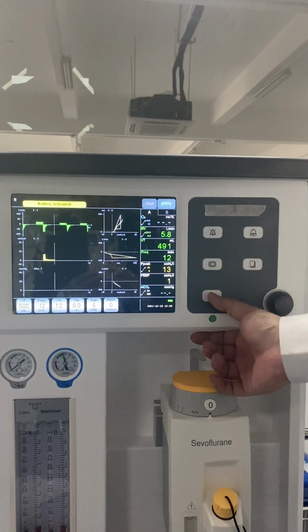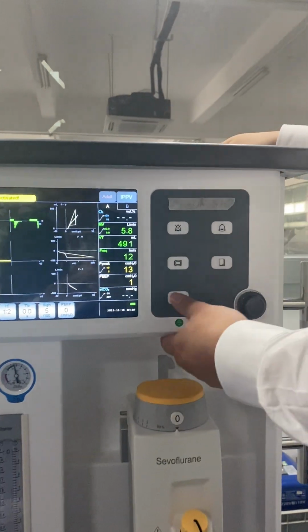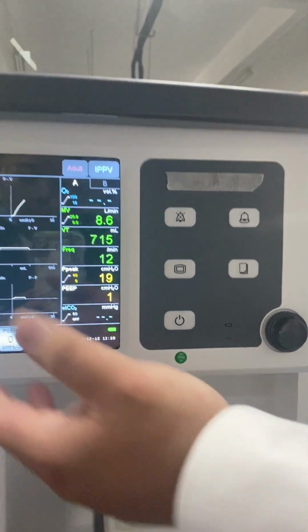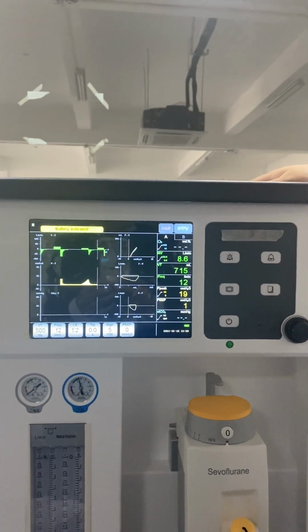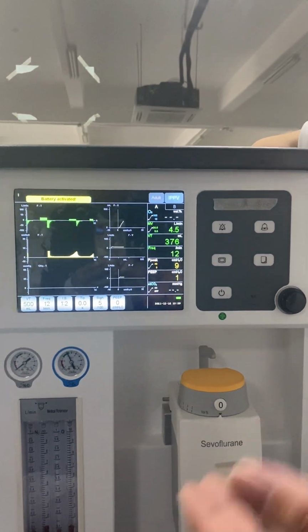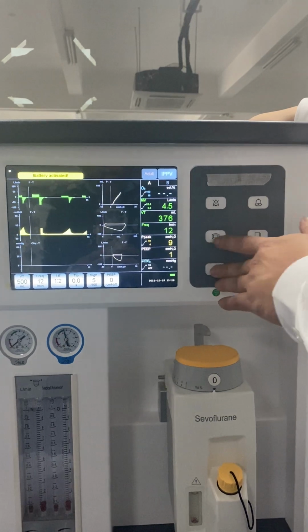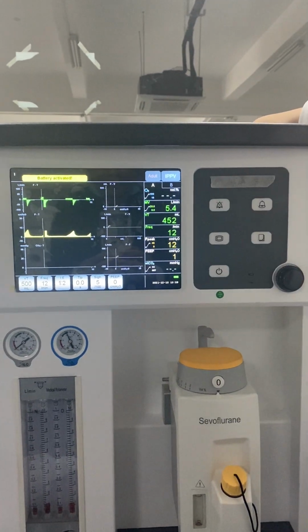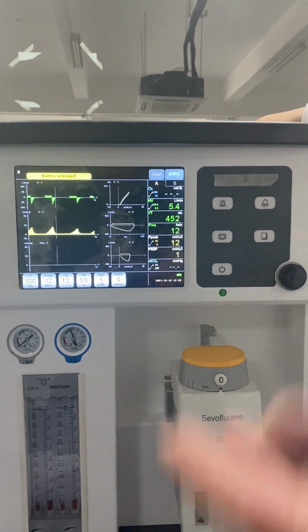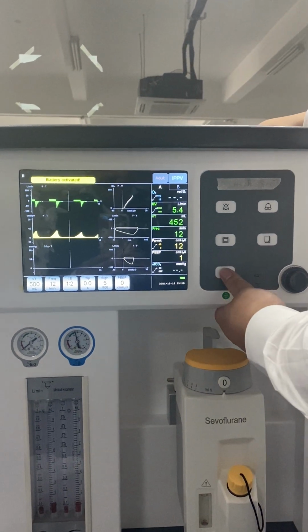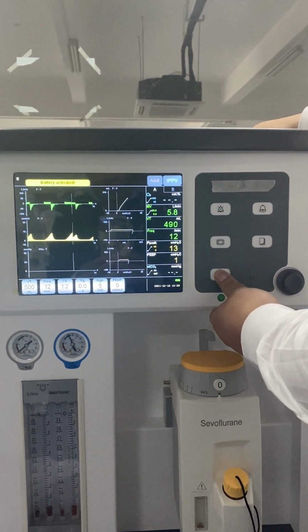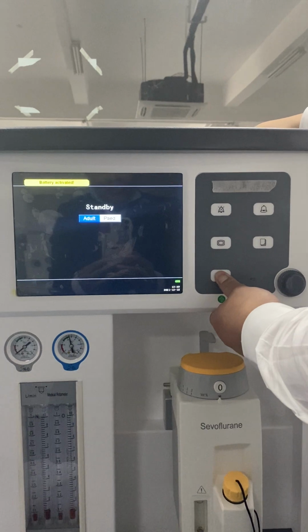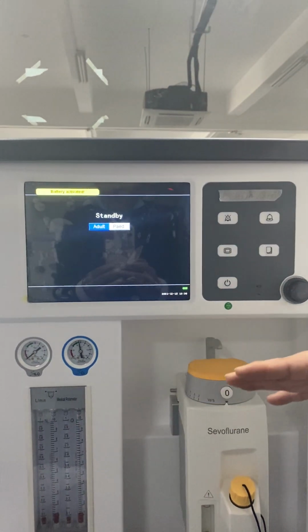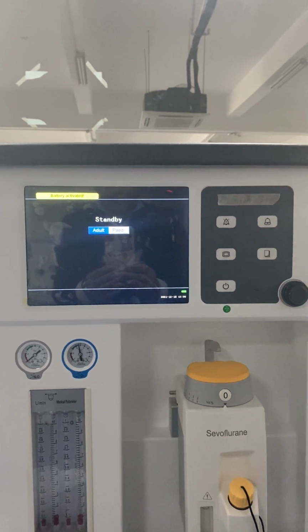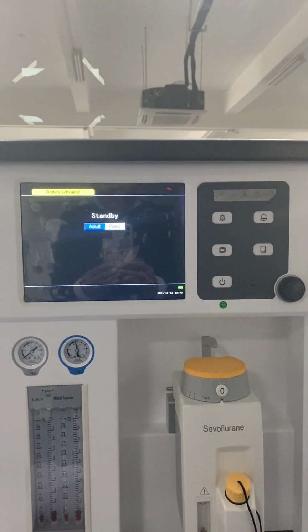And then will be the last button. You can see for this button, if I press it, actually nothing happens, because we have a design here. For example, if sometimes the doctors press the wrong button and it gets into the standby, it means the ventilation stops, then the patient will be in danger. So only if you press this button for 3 seconds, 1, 2, 3, and after 3 seconds, it will enter into the standby interface. So now the ventilation will stop. So this is only used after the operation, or when you want the machine to get a rest.